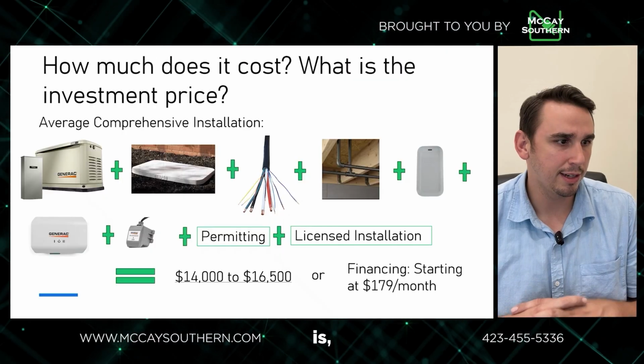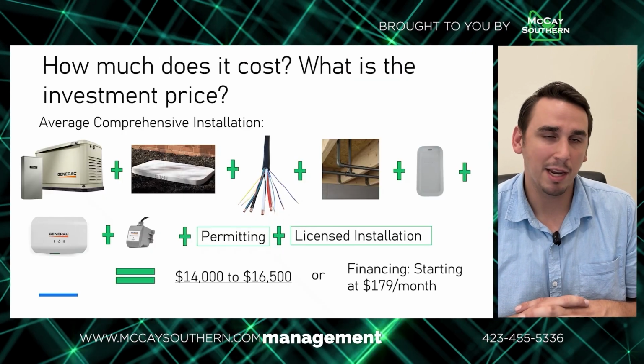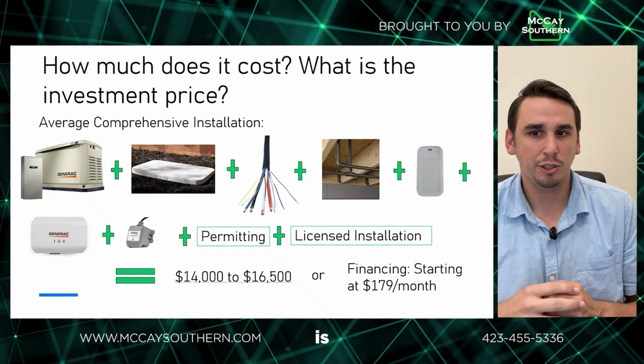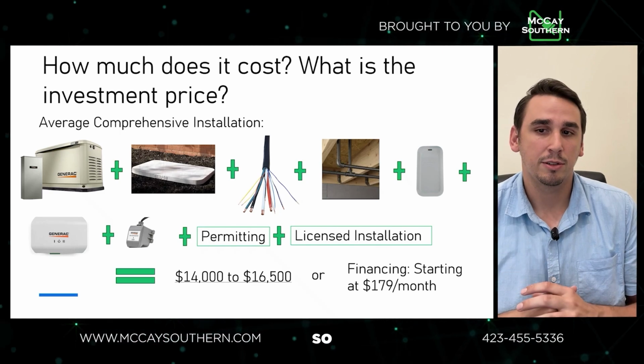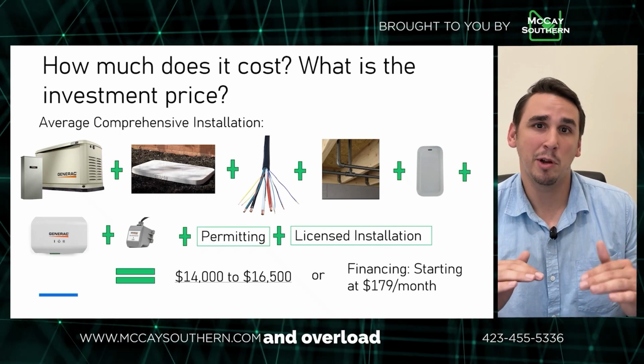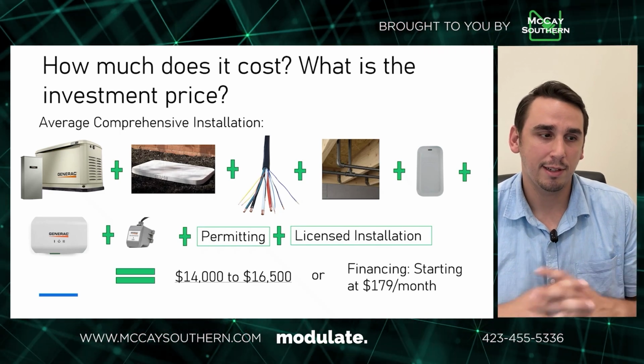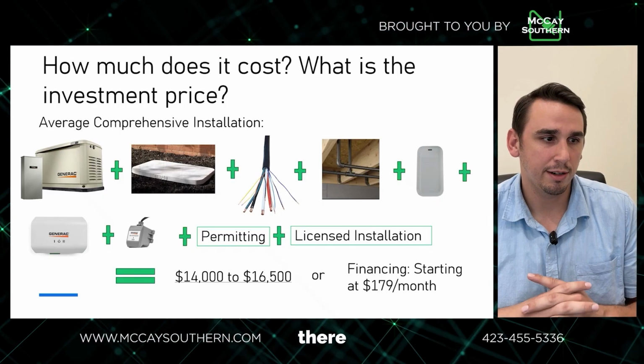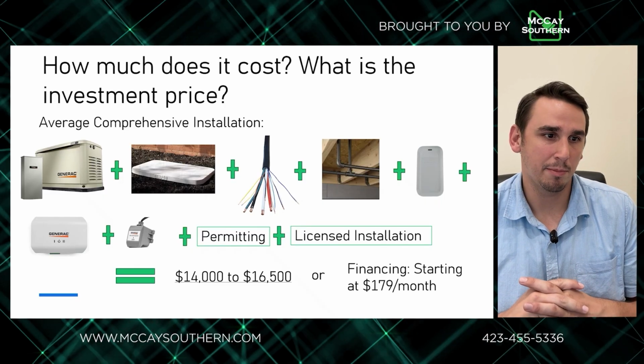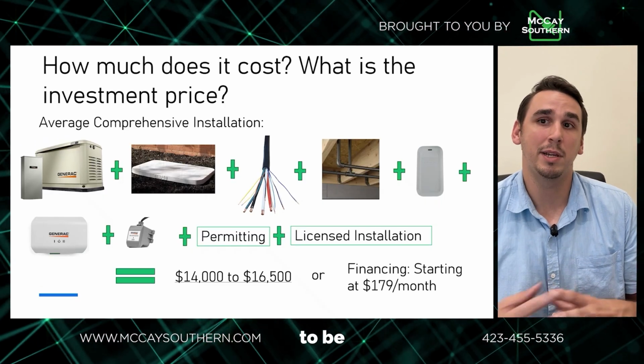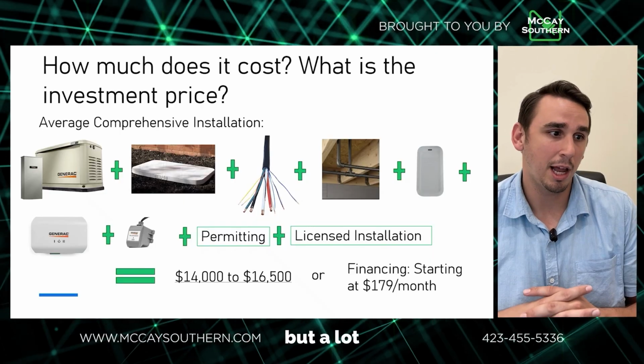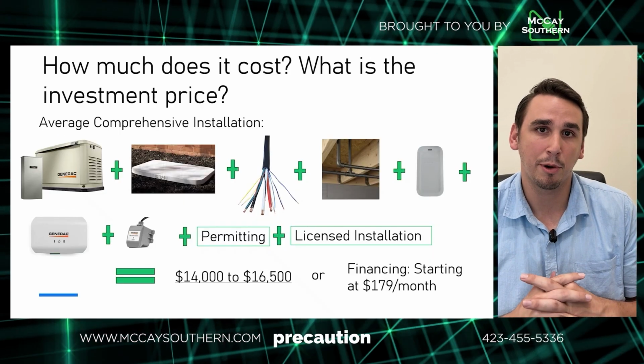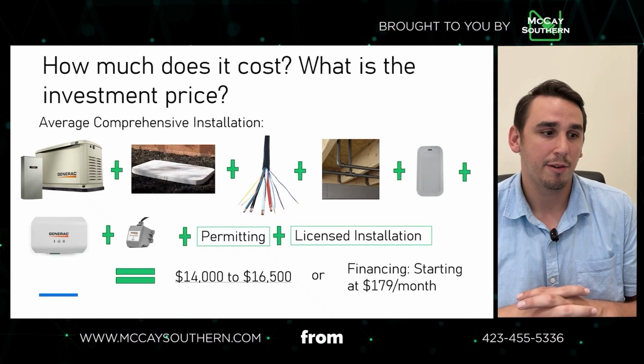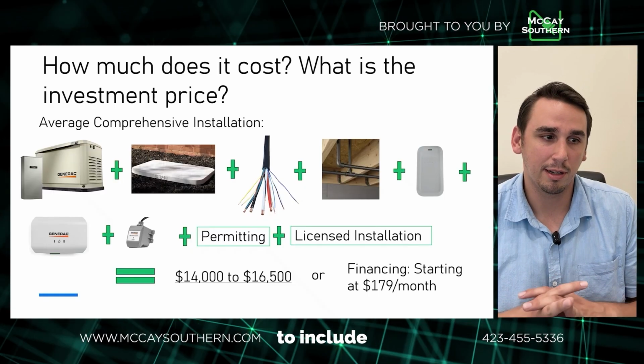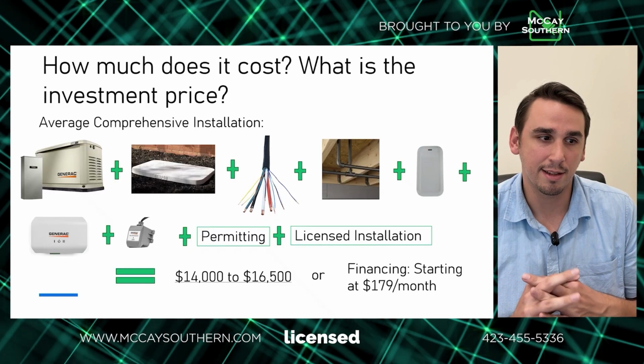The next tool is an HVAC management module. This is used on your HVAC units so they don't kick on at the same time and overload the generator — they self-modulate. The next tool is a surge protection device. Some areas now require them to be electrical code compliant, but a lot of people just want to add that as a secondary precaution against power surges from the road. And then obviously we include permitting and licensed installation.